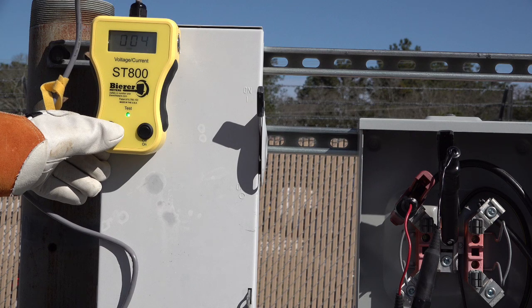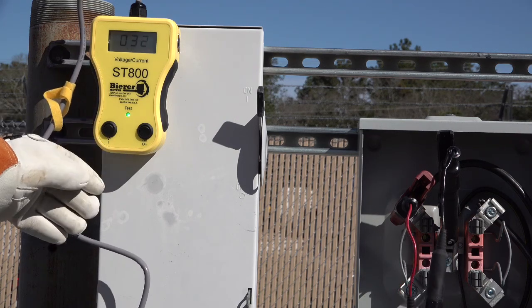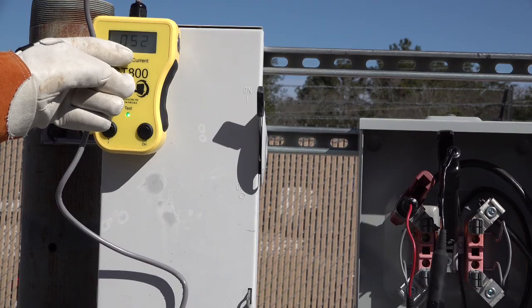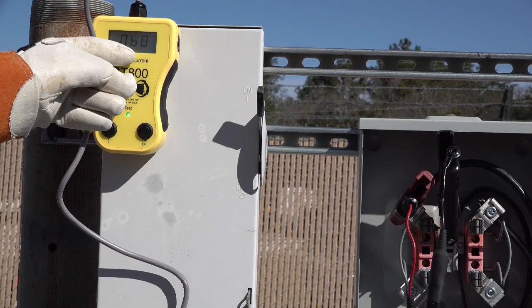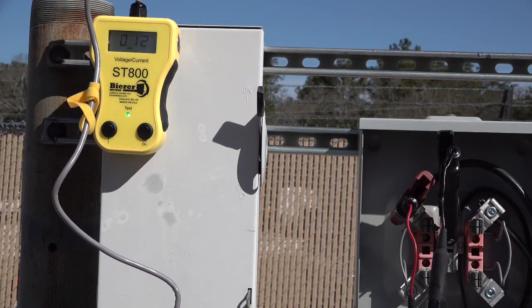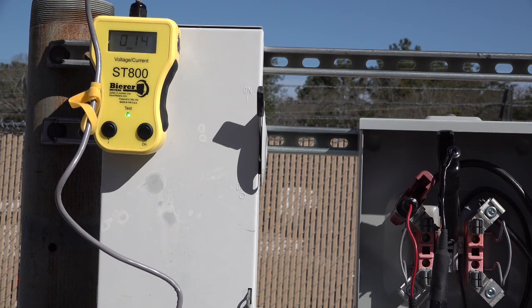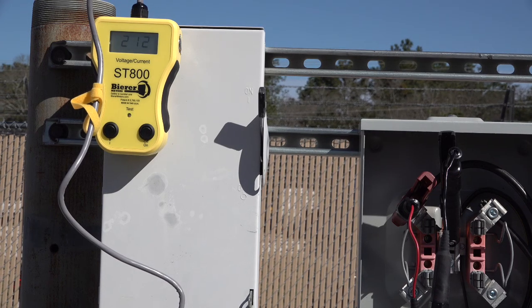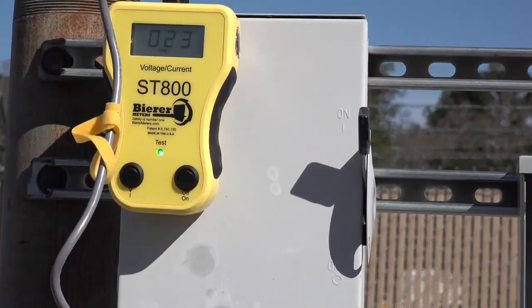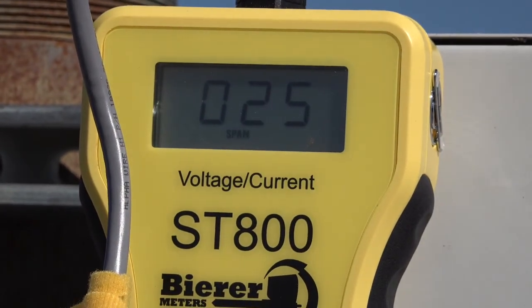Also notice here that the ST800 count is already at 4. In the V or voltage position, the ST800 will alternate between a voltage reading and a count reading. If we flip the V and I switch to the current or I position, it will alternate between the same count reading and a current reading. The maximum count is 158 counts, and I will explain later in the video how the count number can become important troubleshooting information.